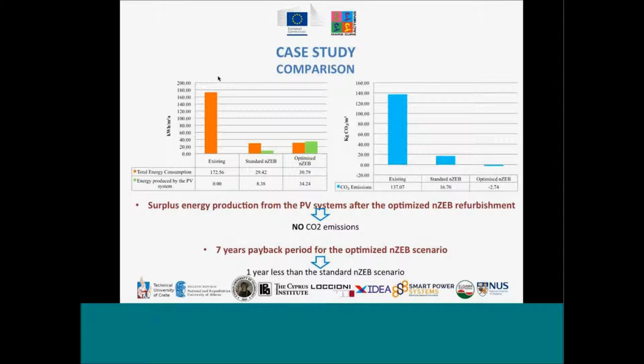Comparing the two scenarios, the standard nZEB and the optimized nZEB, we see the same levels of energy consumption, but with surplus energy production from the PV systems after the optimized refurbishment, and no CO2 emissions. The payback period for the optimized scenario is 7 years, one year less than the standard nZEB scenario. But bear in mind there will be a surplus production of energy from the PV systems every year.